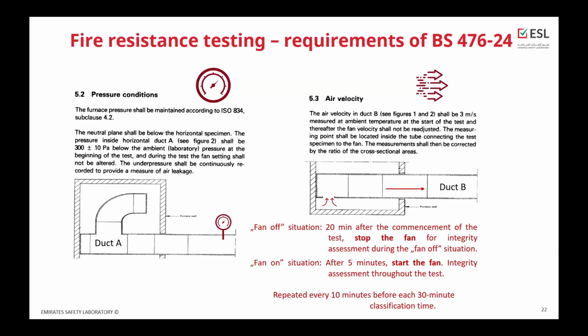The test has two situations: fan on, which is the major part of the fire testing, and the fan off situation. The fan off situation is repeating every 10 minutes before each 30 minutes of the classification time. So for example, 20 minutes after the start of the test or 50 minutes after the start of the test. The fan off situation is simulated by stopping the fan for 5 minutes, during which we are assessing the integrity.